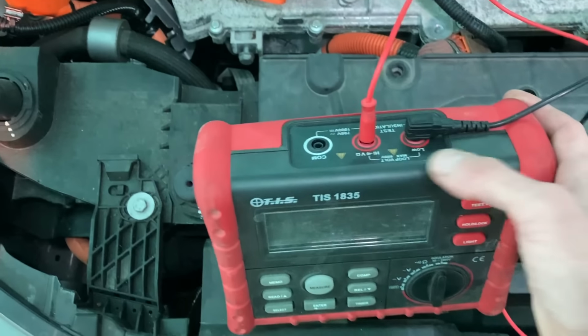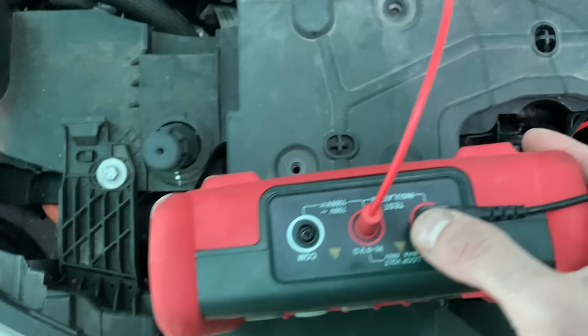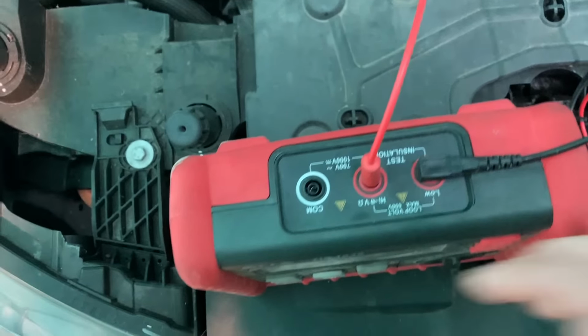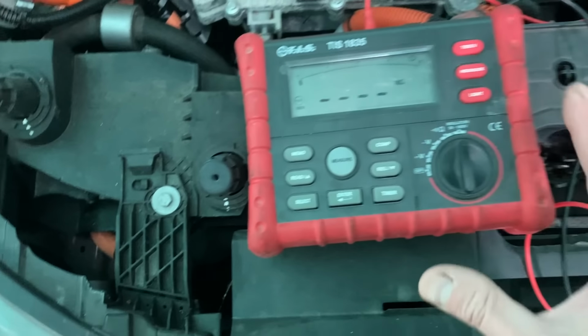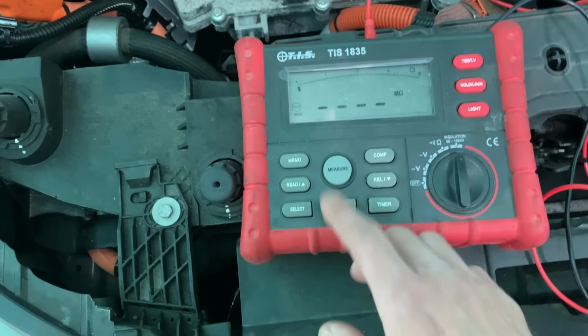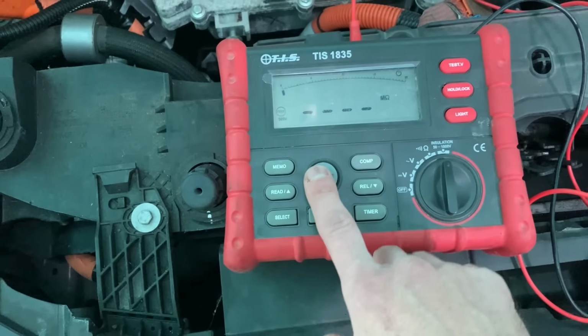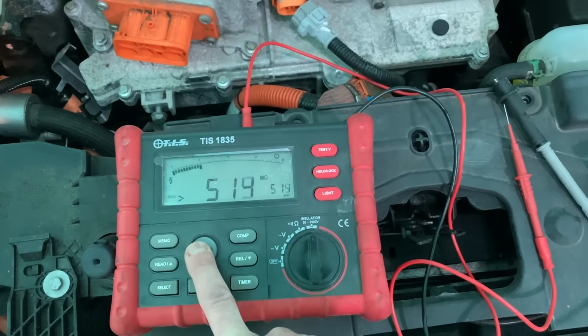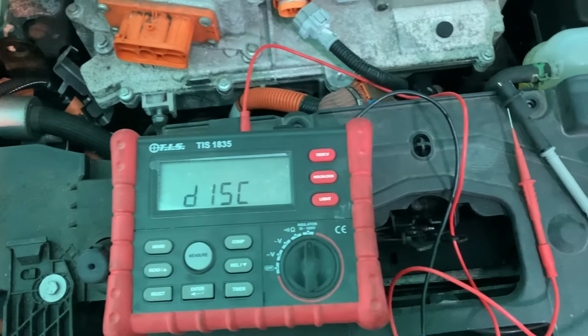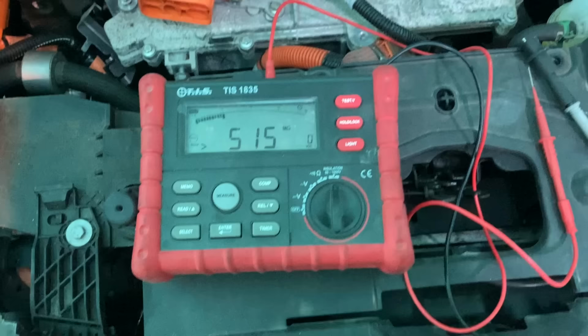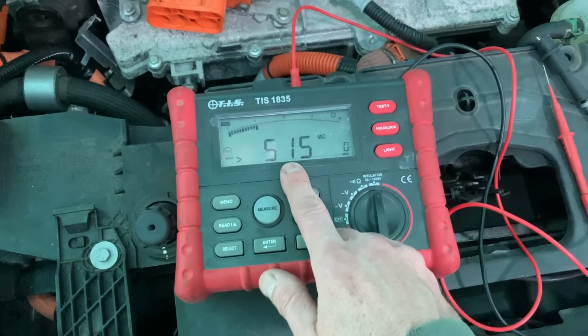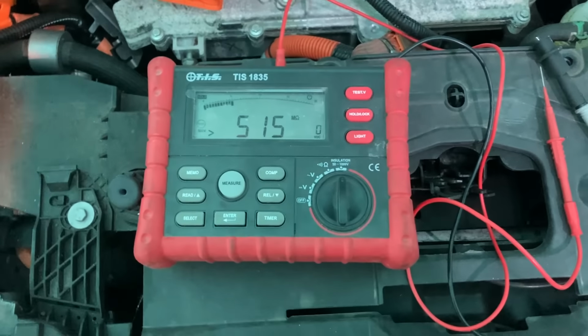First, I've got my leads plugged into the insulation test part, because this is a multimeter and insulation tester. Just making sure we've got it set up correctly - we've set it to 500 volts, and I'm going to press the button. The leads are not currently connected to anything, so they're not together, so we should get a perfect reading. We've got just over 500 mega ohms, so that is literally a perfect reading.